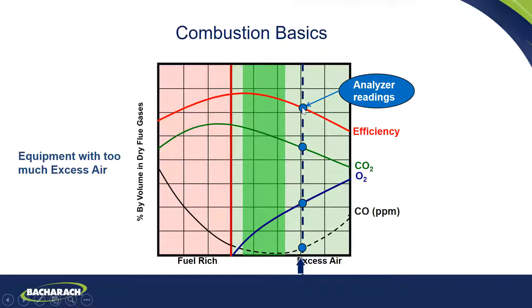Okay. So let's say we brought it to, so this is kind of interesting. It shows the oxygen going down and your efficiency going up because we're going to take the oxygen down to 6%. Okay. That'd be dramatic. It's probably a boiler. So we took the efficiency from 78 to 83. Very good. It's going to save a lot of money on this fuel. CO went up a little bit, but still way within regulations. The important thing here is why taking that oxygen down raises your efficiency. It's because of your stack temperature. It was at 470, we took it down to 390. So now we have 80 degrees of stack temperature that have gone into your system, okay? So you're using that 80 degrees of heat.